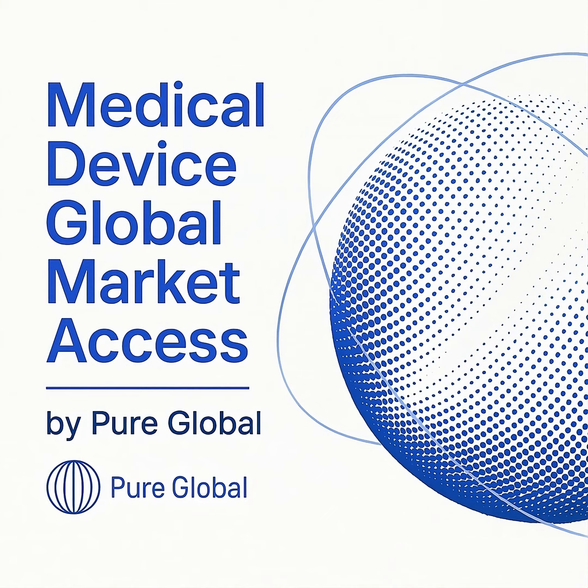File. Furthermore, the QMSR explicitly links compliance with certain ISO clauses to other key FDA regulations. Manufacturers will find that to meet their obligations for identification, traceability, and reporting, they must now ensure compliance with Part 830 for unique device identification, Part 821 for medical device tracking, Part 803 for medical device reporting, and Part 806 for corrections and removals. The new rule makes these connections unmistakable.